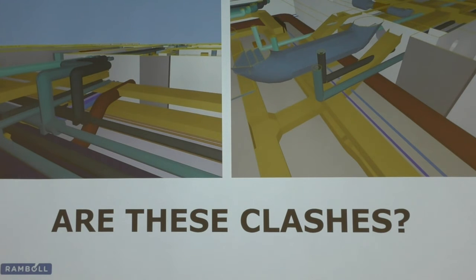If that was a fire compartment wall, then you've got a slightly different thing. So that's quite an interesting thing that people are aware of, the whole thing with Grenfell and the fire compartment walls, and people going for proper sleeves, and you guys are really hot on this. When you put a pipe sleeve or a cable containment sleeve in, they're actually only certified for 200 mil. There's all sorts of distance guidance between them, and I think multi-service openings are a big no-no as well. There's a big problem, so we're trying to figure all that out at the moment.